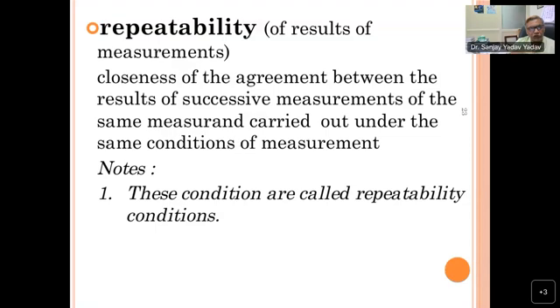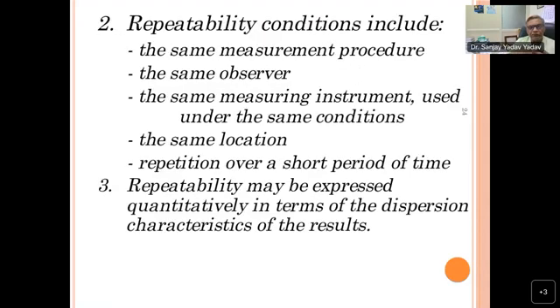So when you have all this, you need to repeat the measurements, and you have to have the repeatability of the measurement. So repeatability of the measurement is nothing but you can characterize it by the standard deviation. The closeness of the agreement between the results of successive measurements of the same measurand carried out under the same conditions of measurement is the repeatability. Then the repeatability conditions include the same measurement procedure, same observer, same measuring instrument used under the same conditions, same location, repetition over a short period of time. So there is short-term repeatability, and there is long-term repeatability.